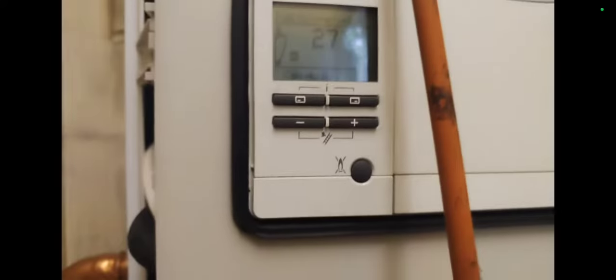It's good if you can to do a gas rate and a working pressure test, because they can tell you a similar thing, but they do tell you slightly different things. So do a full gas rate if possible and a working pressure test. These tests were made for a reason. Okay, I'm checking my low, my mid and my high level in the plant room. It's the room sealed boiler.